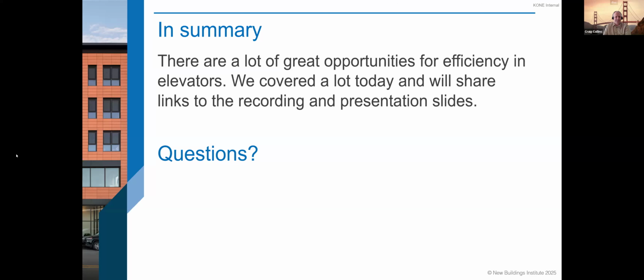I'll let Jeff take a crack at that first. For me, the biggest one specifically around elevator design is honestly just not taking it into account. Because it's such a low portion of the building, not a lot of people pay attention to that small amount of energy from a building standpoint, so it's just not considered. People don't consider that an MRL solution instead of a machine room means less heat, or that a really premium, heavy finish like true marble on the elevator floor makes you jump motor sizes. To me, that's the biggest thing overlooked from an energy standpoint: how much weight matters.